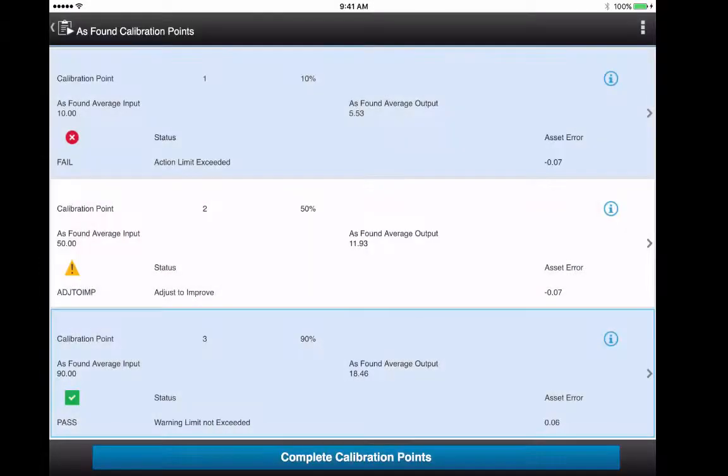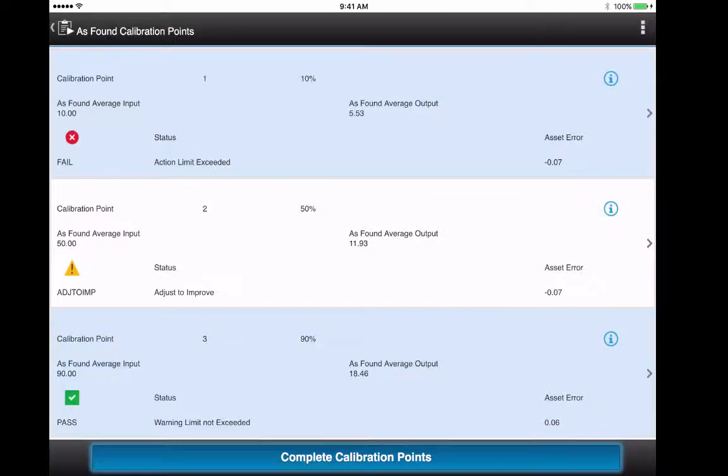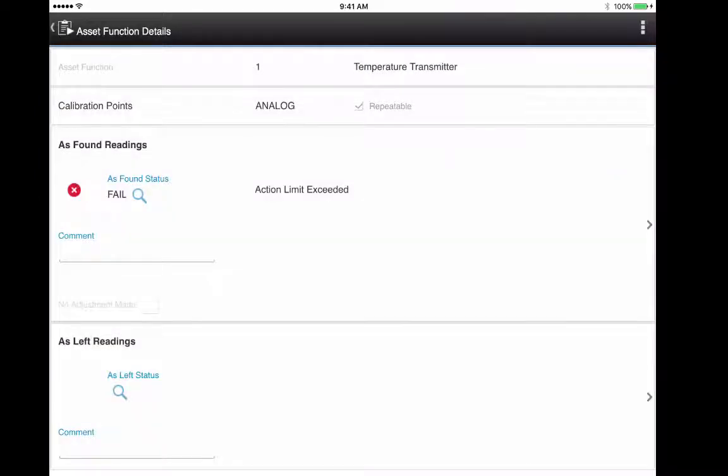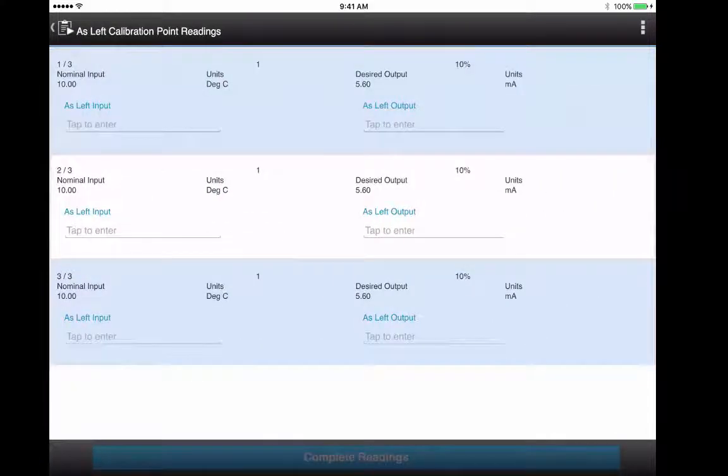You tap the button at the bottom to calculate the as found status. Because the widest tolerances fail, this status has failed. You continue then to do the as left calibration points, pretty much the exact same process.